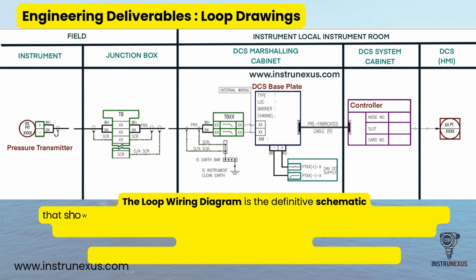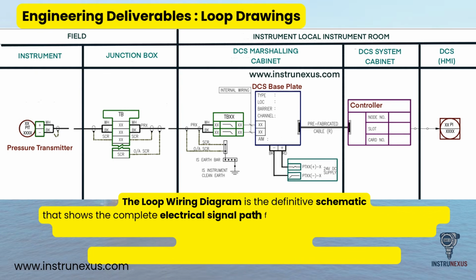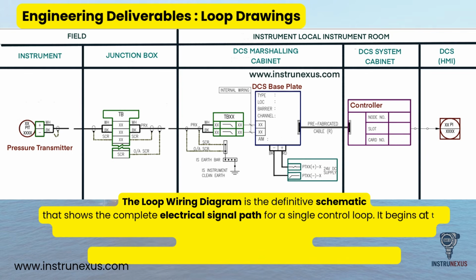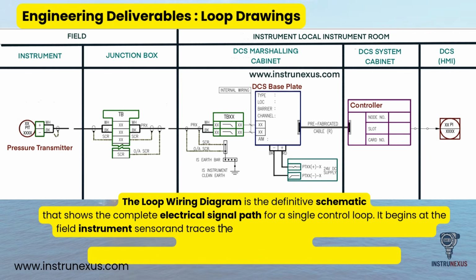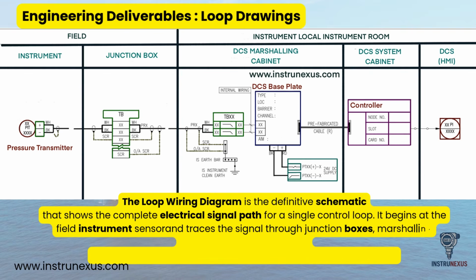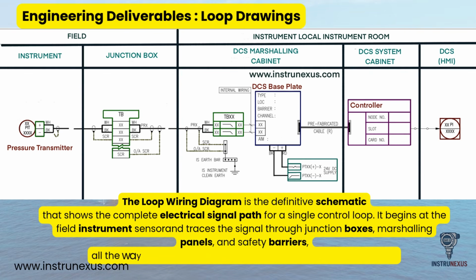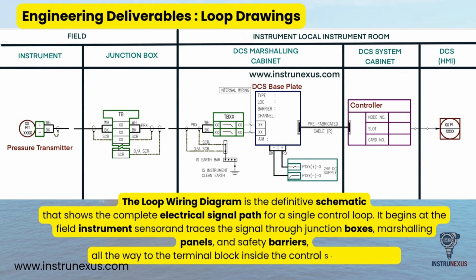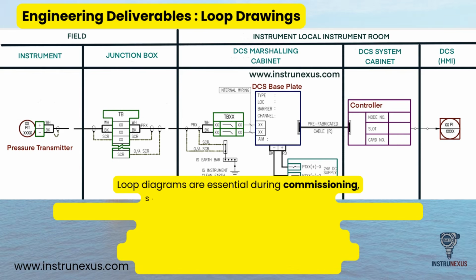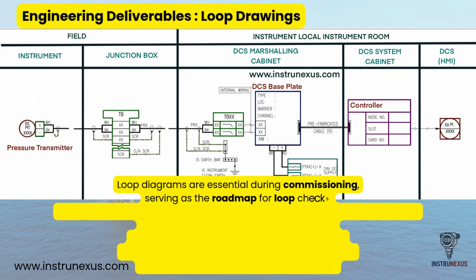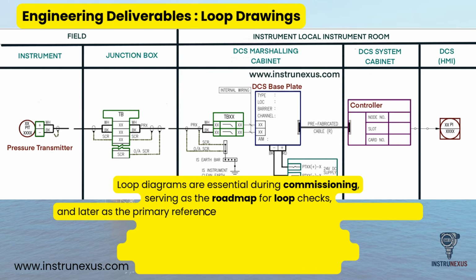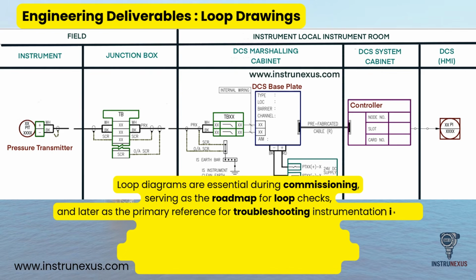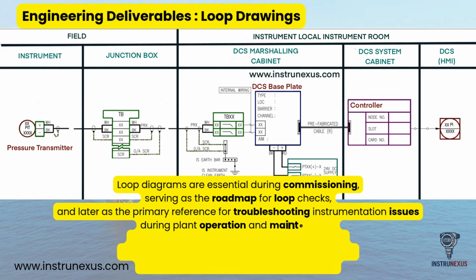The loop wiring diagram is the definitive schematic that shows the complete electrical signal path for a single control loop. It begins at the field instrument sensor and traces the signal through junction boxes, marshalling panels, and safety barriers, all the way to the terminal block inside the control system cabinet. Loop diagrams are essential during commissioning, serving as the roadmap for loop checks, and later as the primary reference for troubleshooting instrumentation issues during plant operation and maintenance.